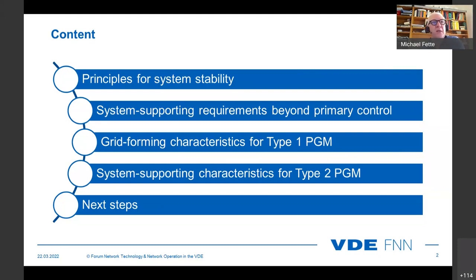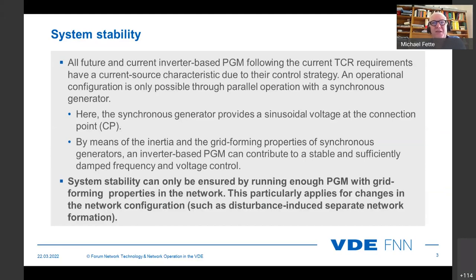So the question is, we have a big problem, let me say. The problem is that the actual machines in the grid are not able to support all the topics we need for stability actions. Mostly they are directed to a control strategy that supports the grid with the maximum feed-in power into the grid, but not to be a part of the control of the frequency of the grid. So we discussed that all future and current inverter-based PGMs following the current TCR requirements have a current source characteristic due to their control strategy. And the classical synchronous machines are also machines we work with in parallel, but they do not support the frequency control in the complete range.